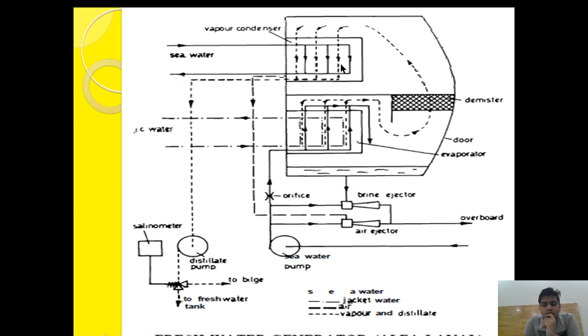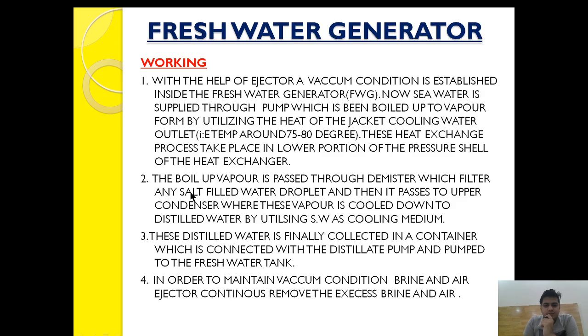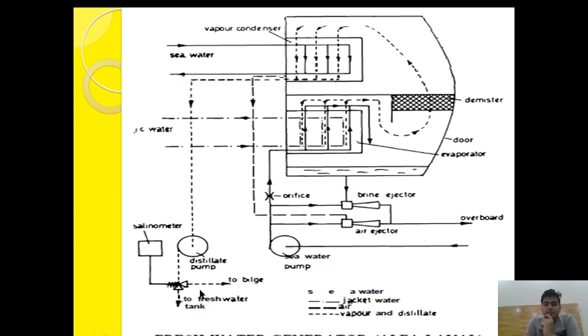The condensed distillate water is collected in a tray provided just beneath the condenser. This collected water is taken out with the help of a distillate pump. The distillate water is finally pumped to the fresh water tank. In order to maintain vacuum condition, the brine and air ejectors continuously remove brine and air.